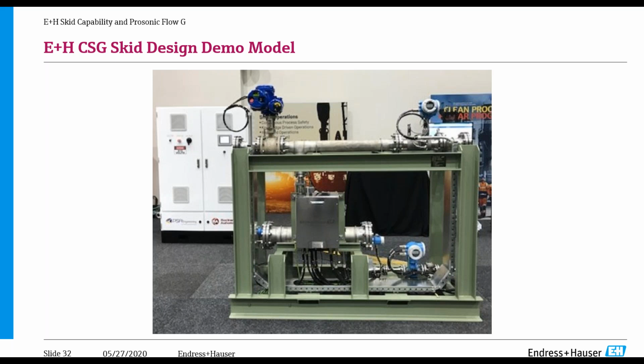You'll see there that we use a Flowserve control valve. We've been working with Flowserve for many years now. And there's actually some subtle differences on this particular valve, particularly designed for the coal seam gas industry, and it's got to do very much with the coupling between the actuator and the valve stem itself. On the standard model, there's some play there within tolerance, but we didn't want any play in between the actuator and the shaft to ensure that we had very fine control. And this has to do with when we're starting up the well itself. In addition to that, there's been a number of firmware updates on that actuator to increase the accuracy of control on that flow meter.